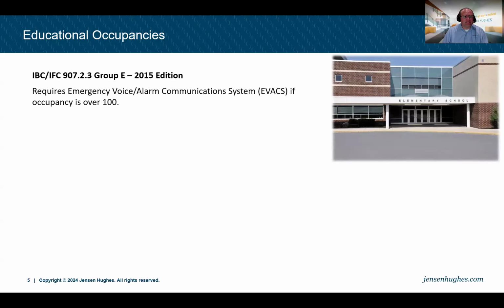Now, when we look at the International Building Code and International Fire Code, an E occupancy is an educational occupancy. It's used for the education of 6 or more persons, from the 0 to the 12th grade. So we're talking about our primary K through 12 schools. Now, as of 2015, these facilities are required to have a manual fire alarm system with an EVACS voice system throughout. EVACS stands for Emergency Voice Alarm Communication System, and it means a voice fire alarm system if we have more than 100 occupants in the building, which is actually a pretty small school if you think about it. Now, it includes daycares within places of worship and K through 12 schools as well.